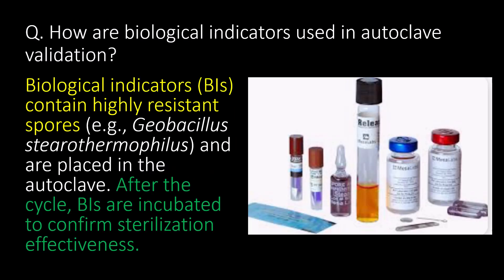How are biological indicators used in autoclave validation? Biological indicators (BIs) contain highly resistant spores — e.g., Geobacillus stearothermophilus — and are placed in the autoclave. After the cycles, BIs are incubated to confirm sterilization effectiveness.